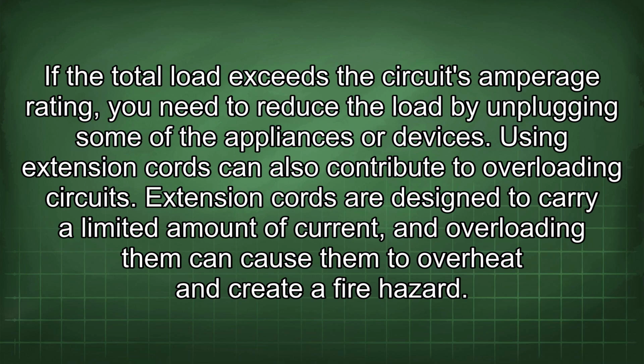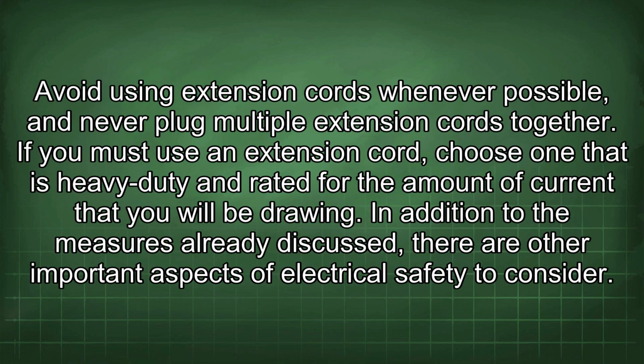appliances or devices. Using extension cords can also contribute to overloading circuits. Extension cords are designed to carry a limited amount of current, and overloading them can cause them to overheat and create a fire hazard. Avoid using extension cords whenever possible, and never plug multiple extension cords together. If you must use an extension cord, choose one that is heavy duty and rated for the amount of current that you will be drawing.